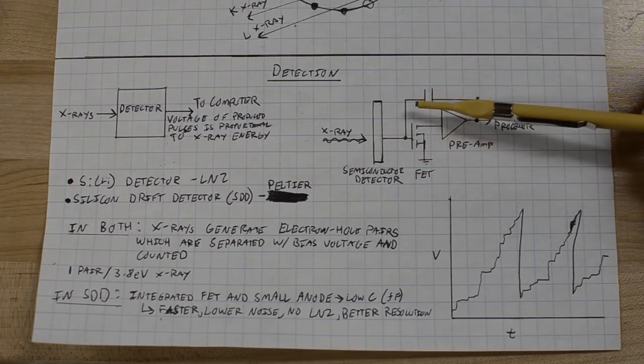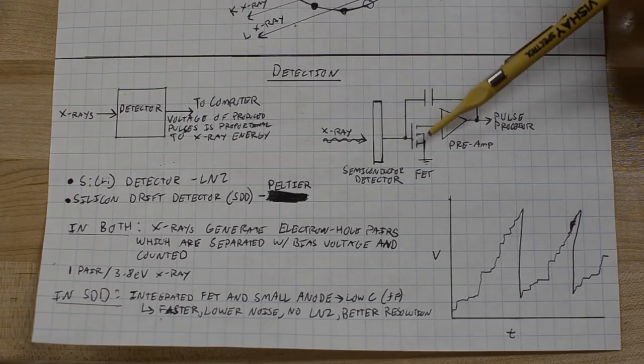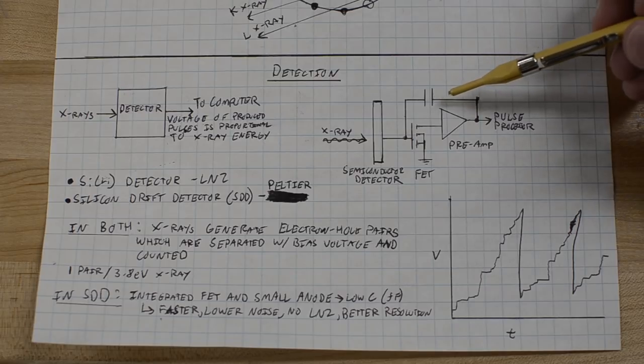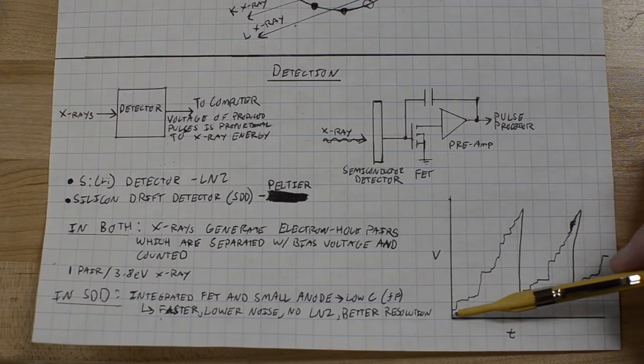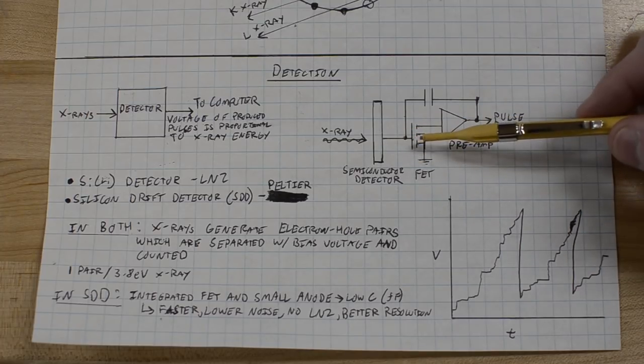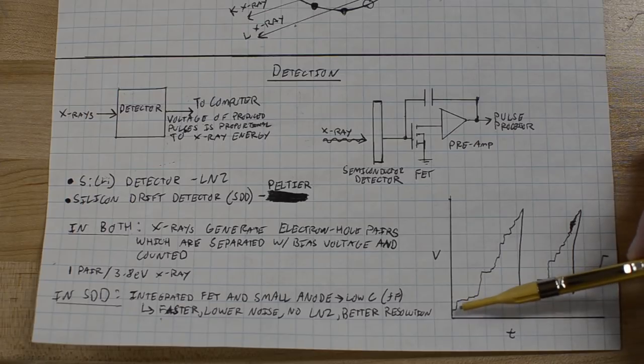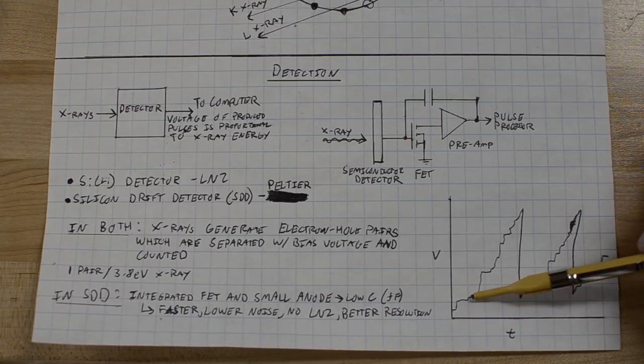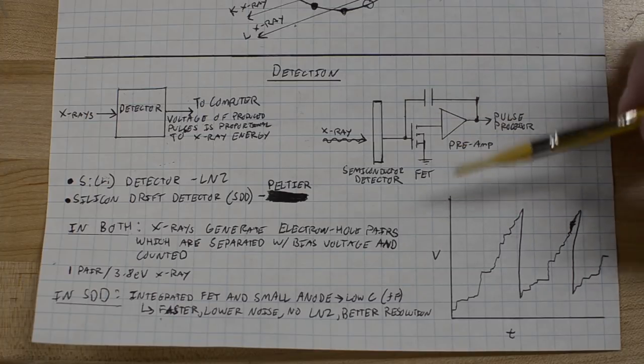There's a preamplifier and a feedback capacitor. For every x-ray event where the hole pairs are generated, swept off to the sides, and amplified, that potential is stored on this feedback capacitor. And after the capacitor fills up, it's basically shorted out, and you'll see in this graph here these rapid downward spikes. As an x-ray of some energy hits the detector, the voltage proportional to that energy created by the detector is stored on the capacitor. That causes these upward spikes in this graph here.